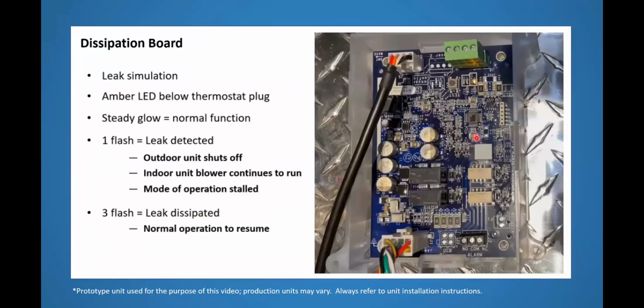This is the same circuit board fundamentally in a rooftop unit, fan coil, furnace, etc. There's 4 places to wire stuff on there. The top on the white up here is the refrigerant leak sensor. That's where it wires. This is factory installed in the evaporator coil and wired to this board.